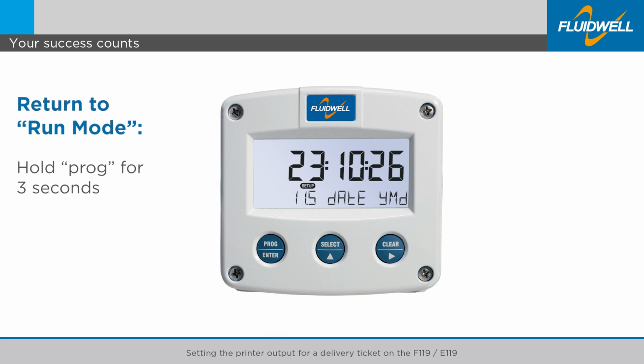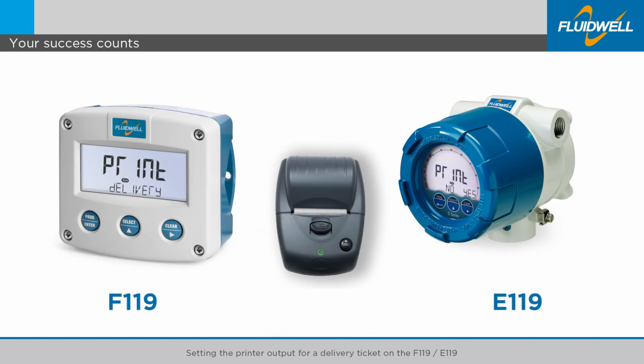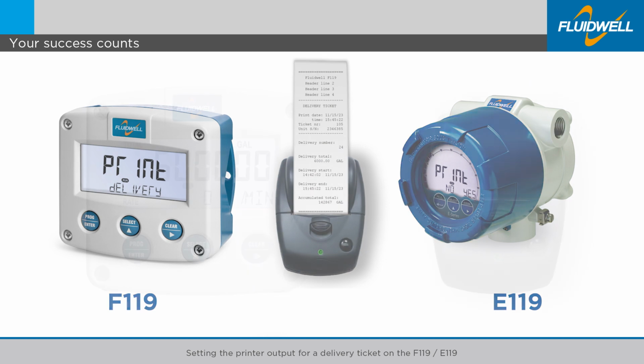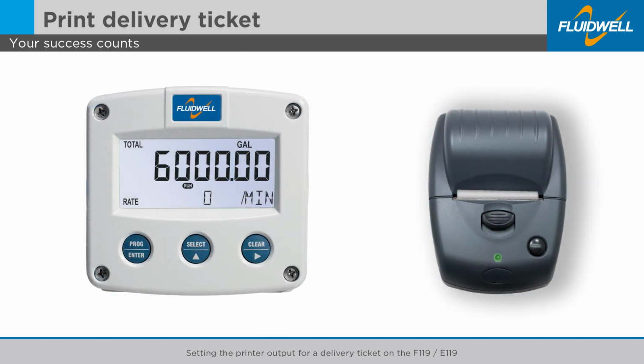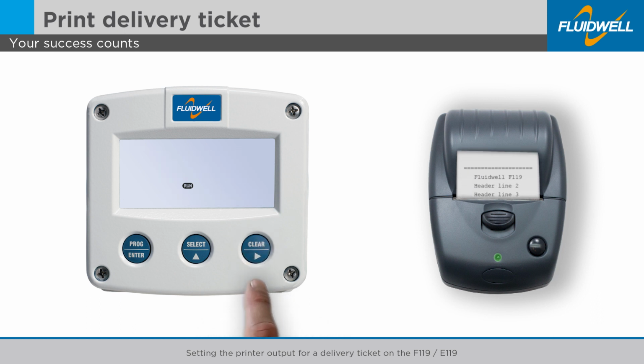Now all is set, we are going back to Run mode. Hold Prog for 3 seconds to exit the Setup menu and return to Run mode. Congratulations! You have now set the printer output to print a delivery ticket after an operator command on the F or E119 flow totalizers. With the delivery mode enabled, the operator cannot clear the totalizer separately, but instead must end the delivery by pressing the Clear key or via the external reset input.